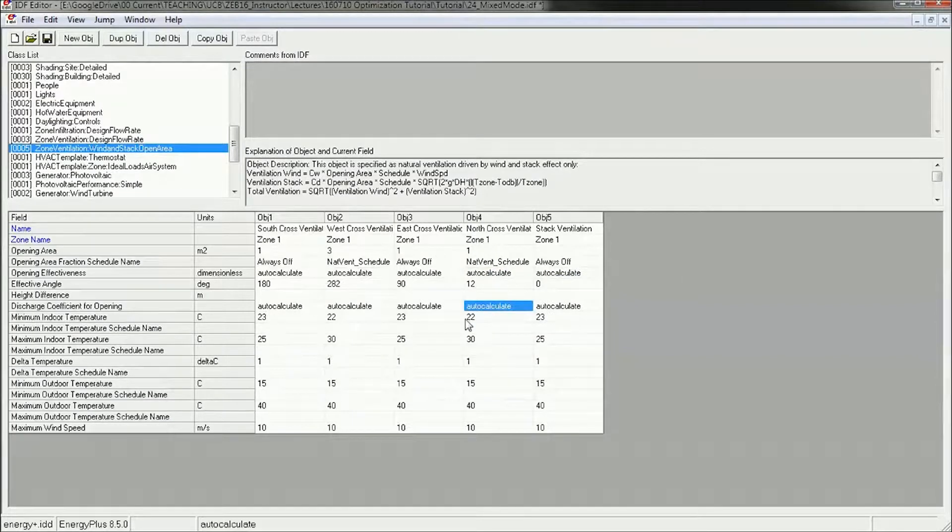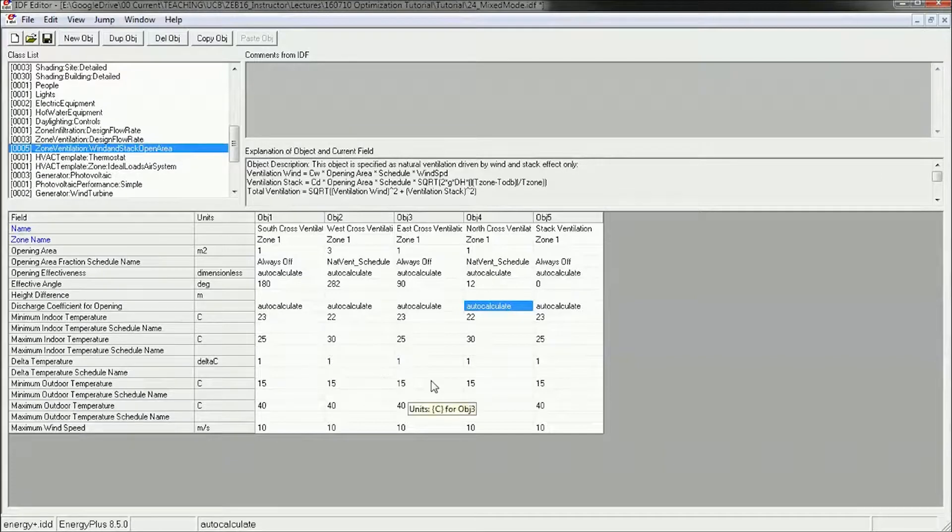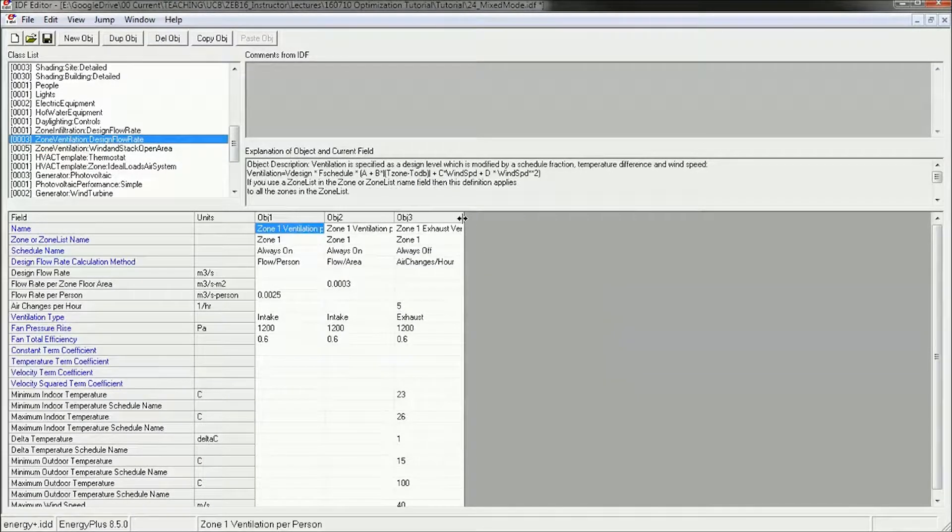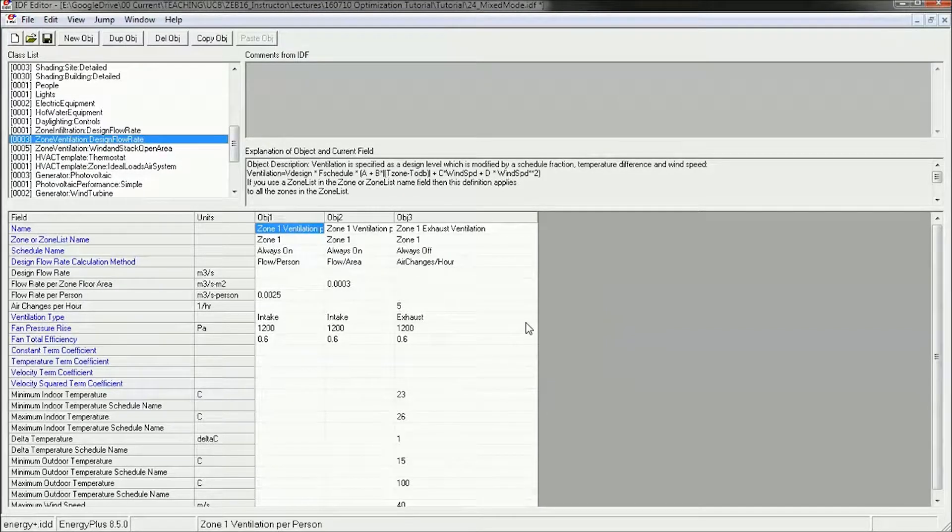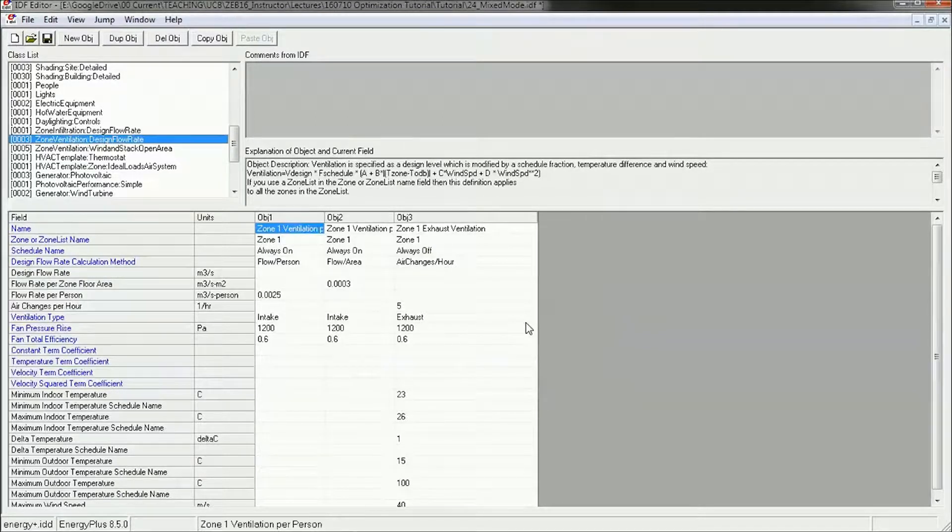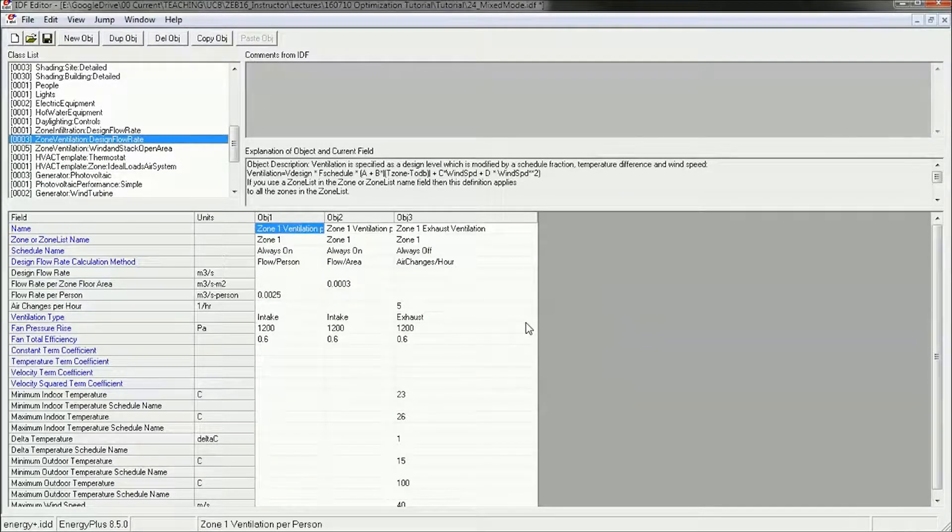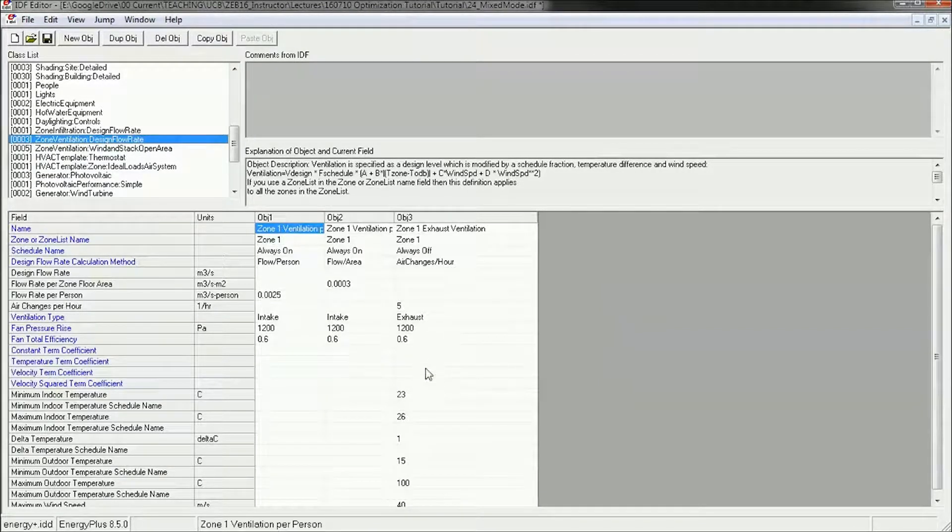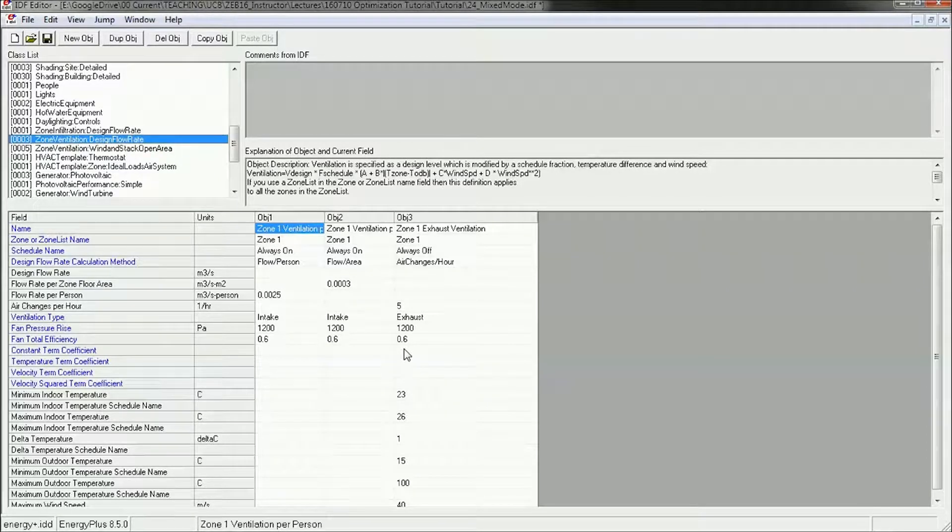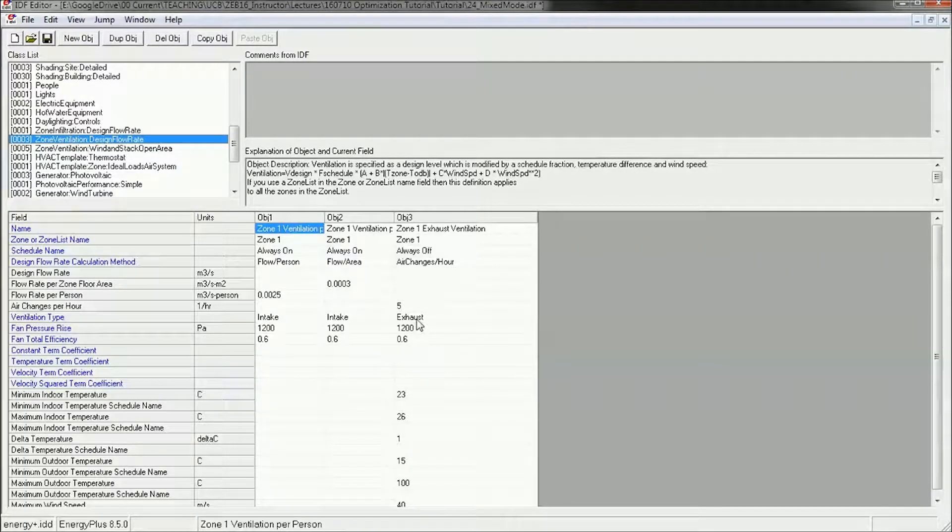And if you don't have windows that are operable, then you can approximate this by using what's called an economizer. And the economizer would be traditionally the fans for your HVAC system would come on but not use the compressor or the coolant or the heating. So you've just got fresh air coming in. And it's a little bit less efficient. Obviously, you're still using a fan, but the fan is not using heating or cooling energy. It's just electricity.